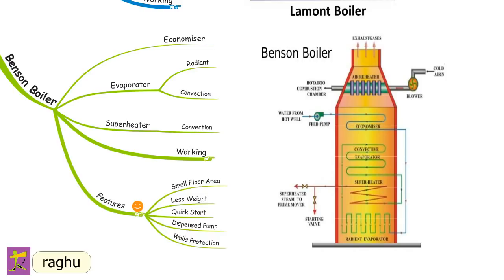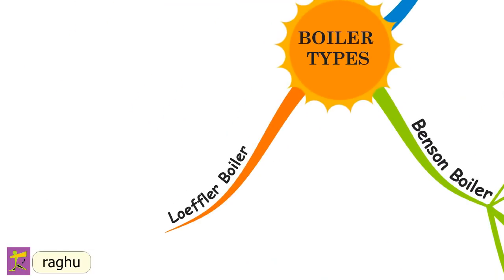Features of the Benson boiler: 1. It can be erected in a comparatively smaller floor area. 2. As there are no drums, the total weight is 20% less than other boilers. 3. It can be started quickly. 4. Circulating pump and downcomers are dispensed with. 5. Furnace walls can be more efficiently protected using smaller diameter, close-pitched tubes. 6. Easy transportation is possible. 7. It can be operated economically by varying temperature and pressure at partial loads and overloads. 8. It has only 4% blow-down losses. 9. No special starting superheater arrangement is required.